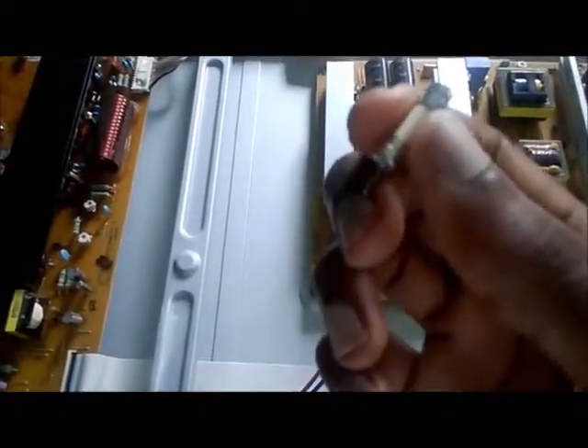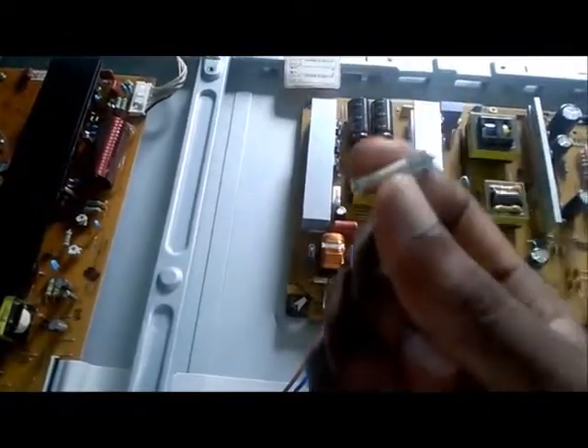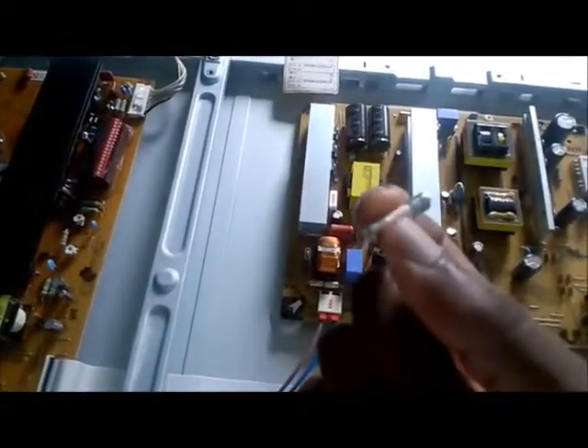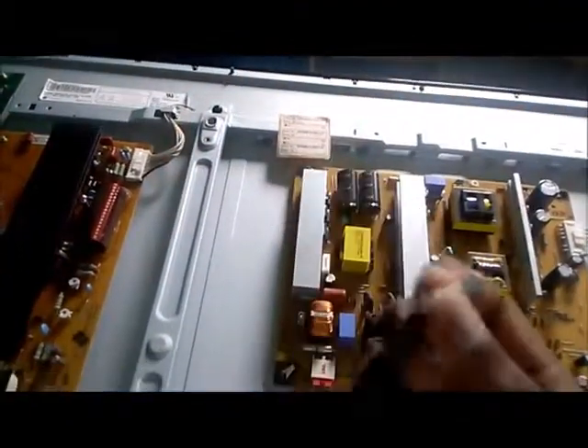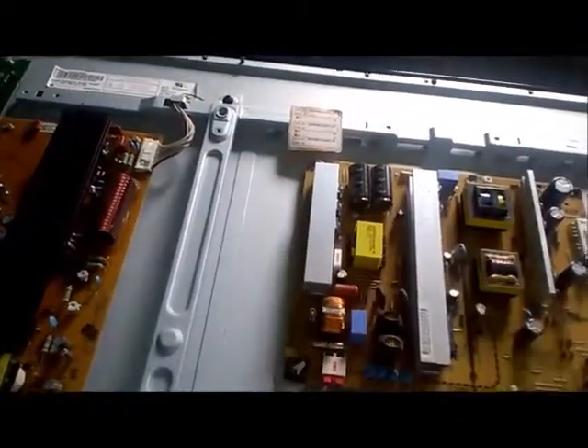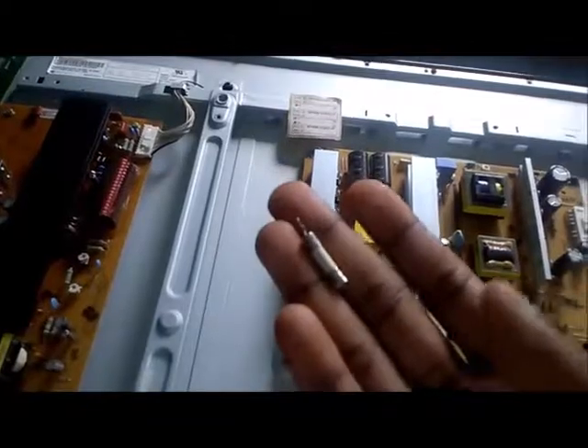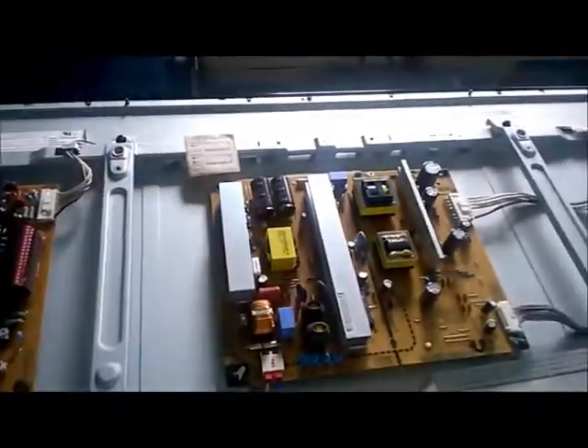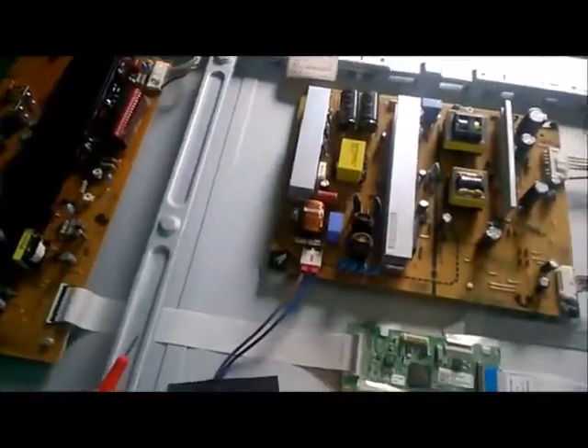Normally with the fuse there is a small wire that runs inside from end to end. When the fuse is blown, that wire will break. When the wire breaks, there is no connection, so that's why we didn't get any reading from this fuse. This fuse is blown.